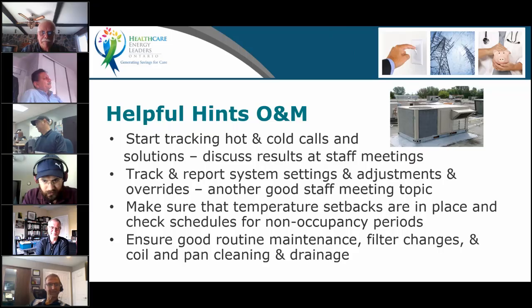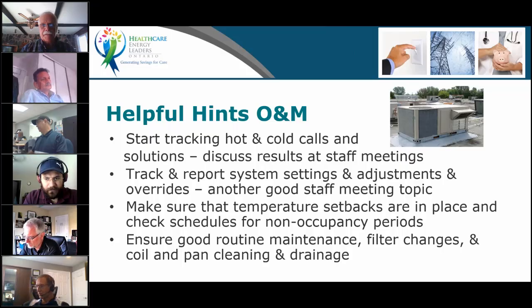If you've got a gas heated building and you can set back a portion of it, if done properly, I'm not saying setting back crazy so that people freeze in the morning or after a weekend, but doing it properly is guaranteed to save energy. I've had so many arguments with operators. They say, hey, setback doesn't save energy because my boiler just runs for an hour straight when I come back. Well, it did not run very much when you were not there. That's why it's running an hour straight now.